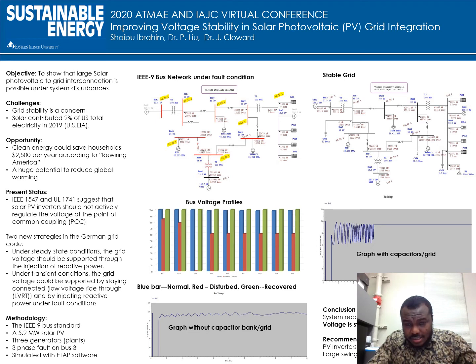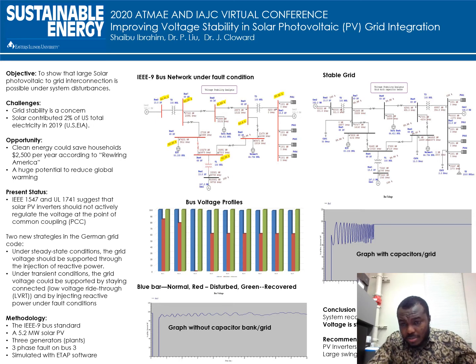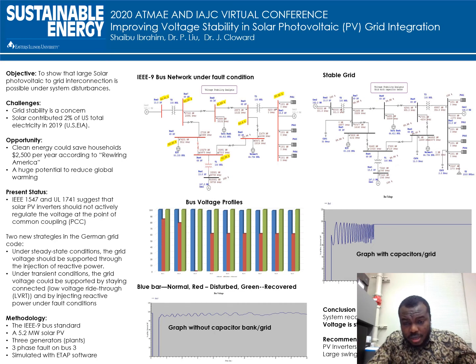The stable network result shows that the system is now stable with the introduction of capacitor banks on bus number three, bus number six, and bus number seven, as well as the system connecting to a larger grid on bus number three. After the fault was cleared with the introduction of capacitors and the grid connection, it took a much shorter time for the system to return to stability. As seen in the second graph, the system was recovered in about 2.9 seconds.